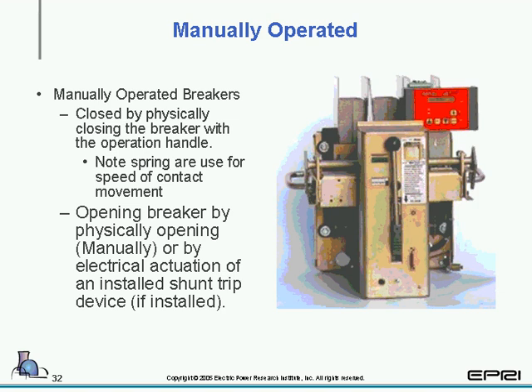And we'll start looking at power breakers or metal-clad switchgear. The very first one we'll take a look at is the manually operated breaker, closed by physically closing the breaker with the operation handle. Opening the breaker by physically opening it manually, or by electrical actuation of an installed shunt trip device. So even though a manually operated breaker may have electrics associated with it, most designs typically say it's manual depending upon how it's closed, not how it's opened.